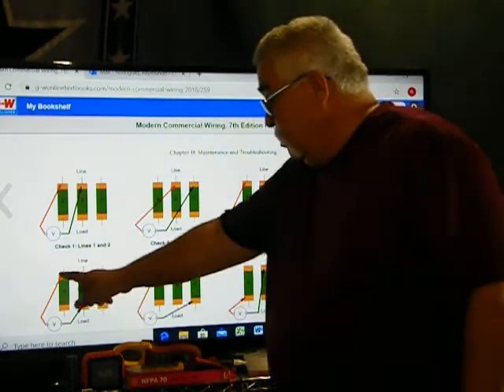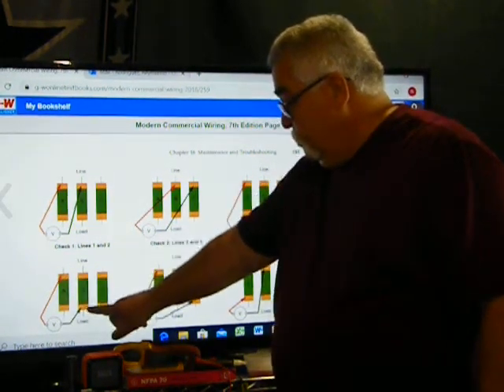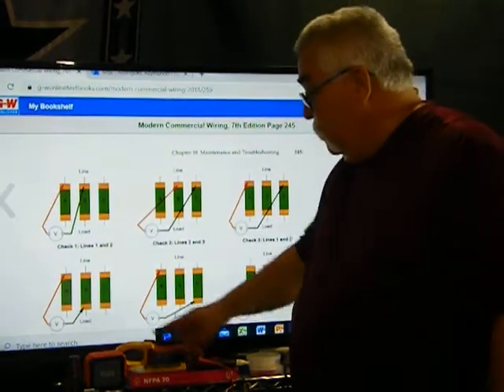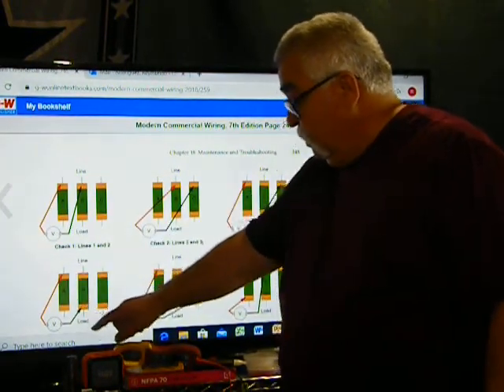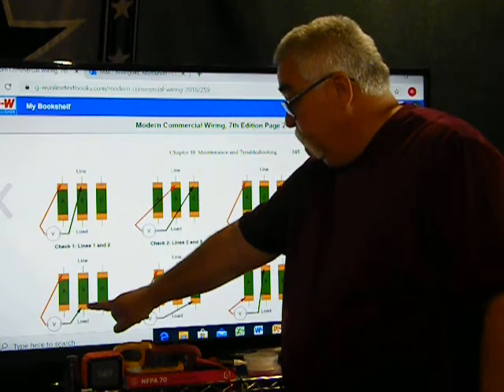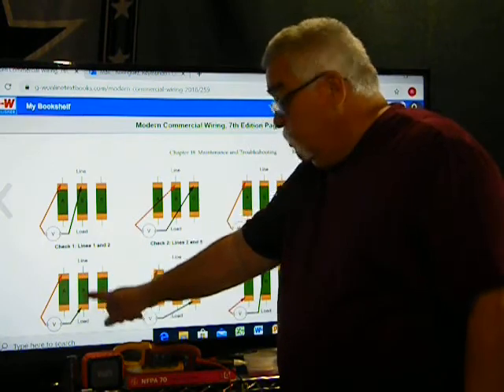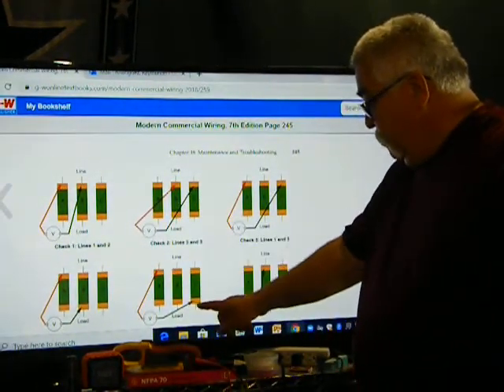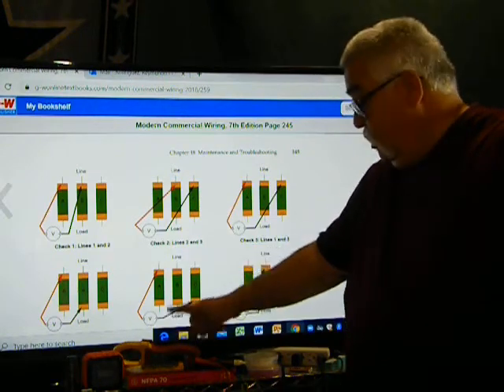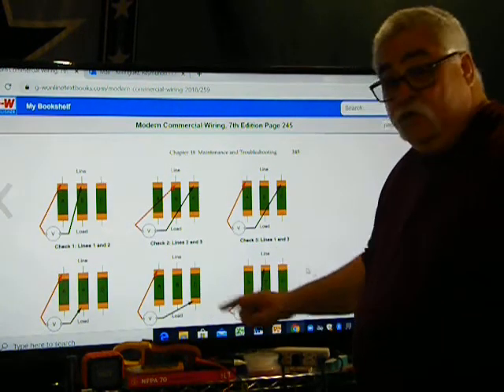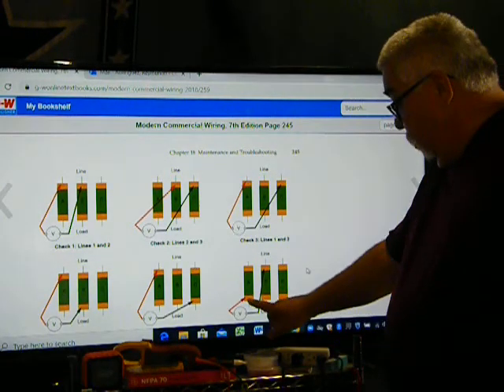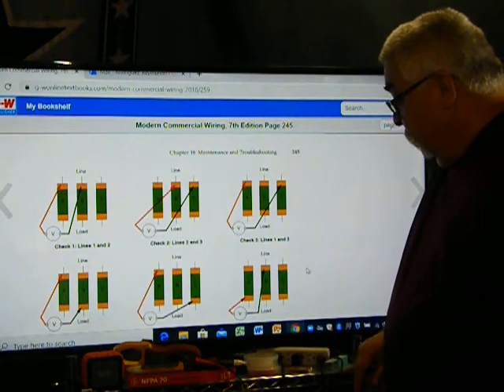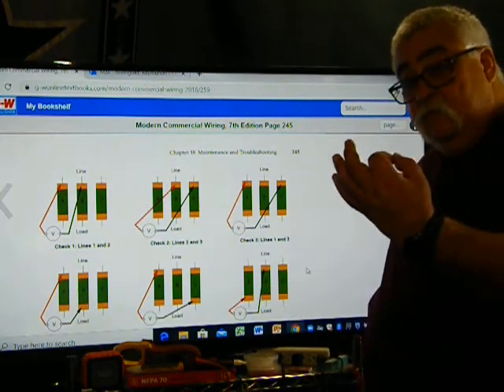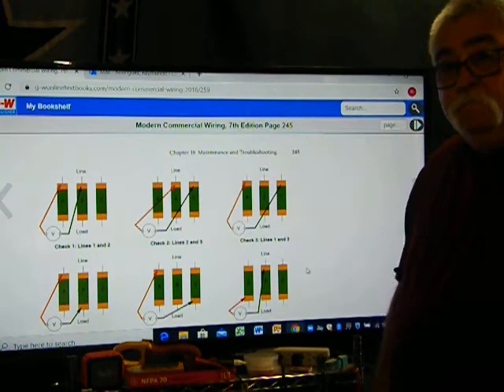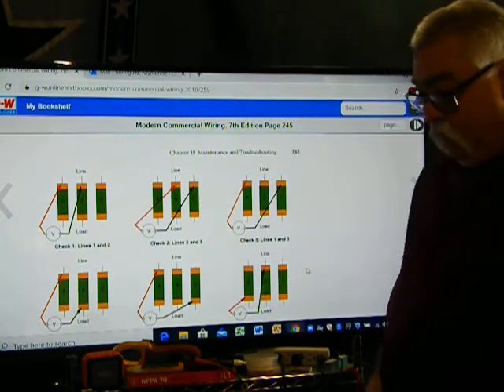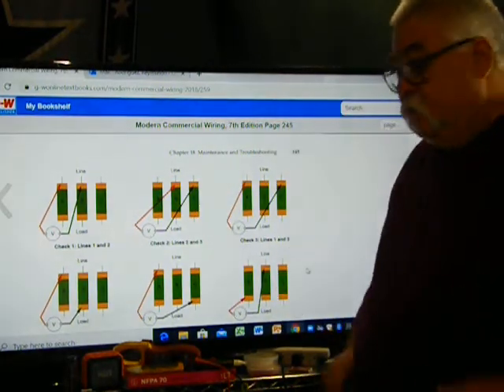So let's say I measure A to B, top hot to switch leg, or whatever you want to call it. So this is my line side, this is my load side. So I'm going from my line side to my load side. If I got 480 volts in my meter, that means this fuse is good. I come over here from A to C. If my voltmeter is reading 480, then C fuse is good. All of a sudden I go from A load side to B line side, all of a sudden I get 0. Well, that means that my A fuse is bad. Okay, so this is how you can test.